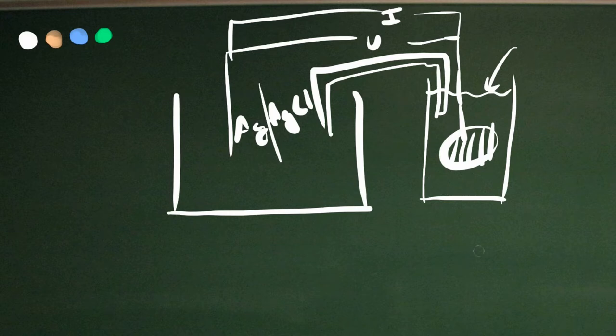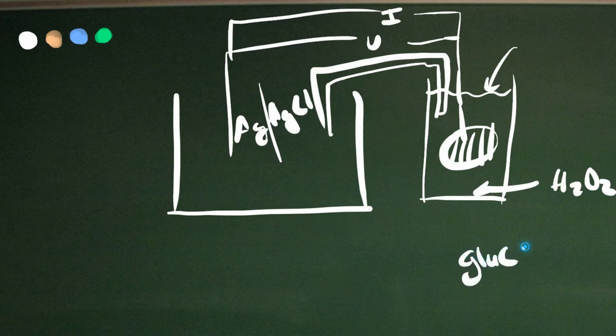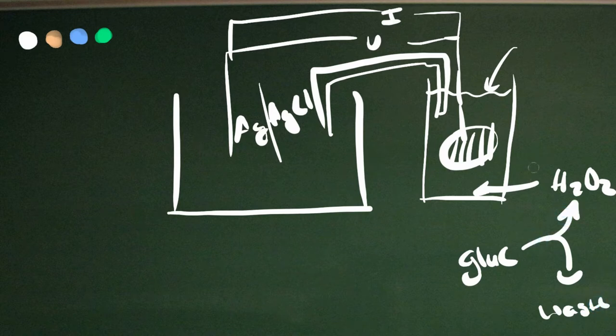So if you change the battery chemistry by, say, adding hydrogen peroxide, then the voltage and the current will change accordingly. But how can you add hydrogen peroxide? Well, it turns out there's a little enzyme that very specifically recognizes glucose and converts it, and it produces one molecule of hydrogen peroxide. So what we have here is an enzyme, actually a bioengineered enzyme at this point, that is really the workhorse of this measurement. It's that enzyme that specifically grabs glucose and makes hydrogen peroxide.